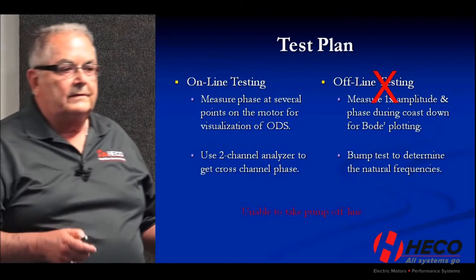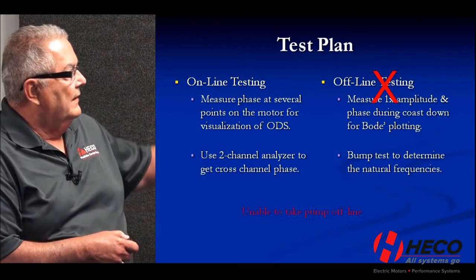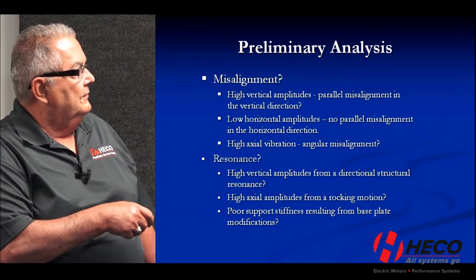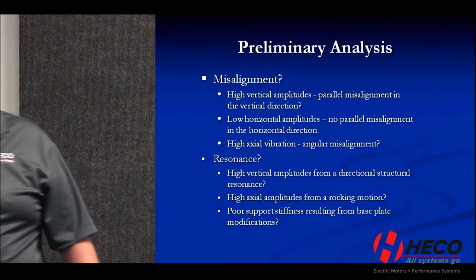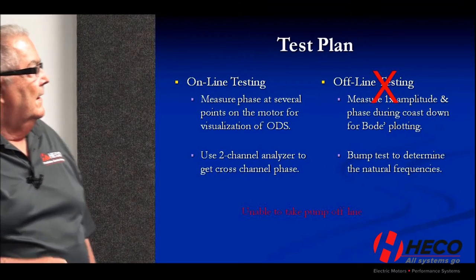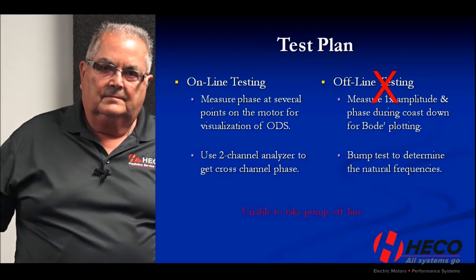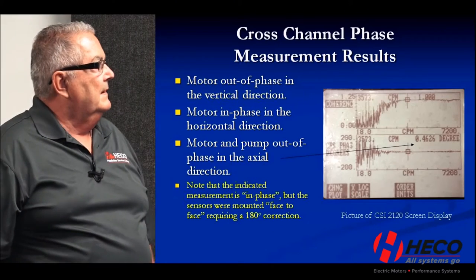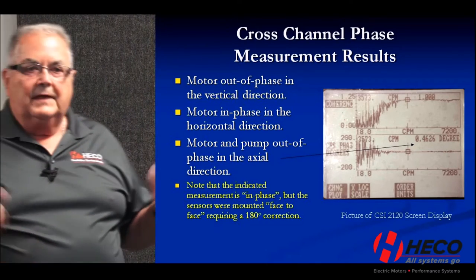The question was what did the horizontal look like relative to the vertical. The high ones were the vertical and the axial; the horizontal was low. Offline testing — like a bump test to check for resonance — was not something the customer was happy about doing first.